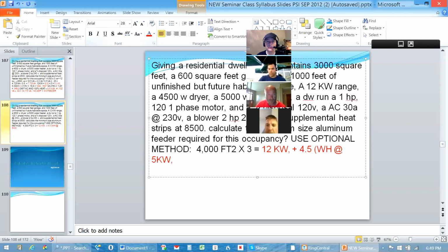So the next thing is going to be B, which is ranges, wall-mounted ovens, and so on and so forth. I'm going to add plus 12K, and I'm not derating it. The table on the right-hand or your left-hand side does not apply under the optional method of calculations. I'm taking the nameplate rating at full face value. No derates. So 12 kW for the range. Then on the dryer, which is the next thing on the list, which is also section C there, I'm going to take the 4,500 nameplate rating, not the minimum 5,000, because that does not apply in the optional method. It only applies to the standard. 4.5 kW for the dryer.